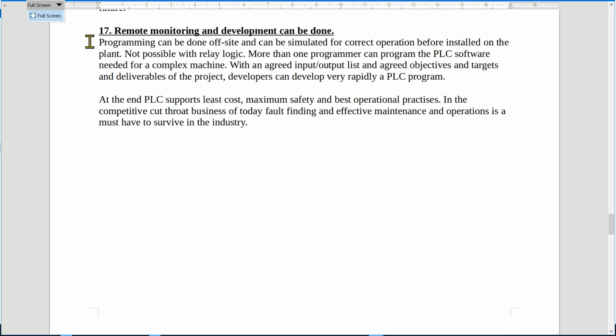With hardwiring logics, all the artisans must be on site. They must be wiring the panel. It's always a challenge because only one person can get into the panel. So there's a lot of delays when you do hardwiring control panel. But today, with our technology, programming can be done off-site and can be simulated for correct operations before you even install it on a plant. And this is not possible with relay logic.